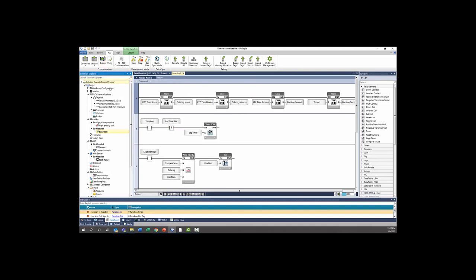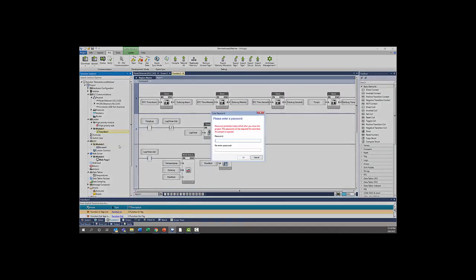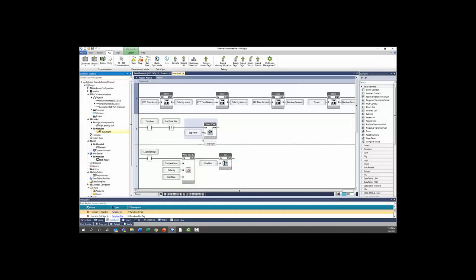In Unilogic, you can also add passwords to the ladder and to the HMIs by hovering over whatever function or HMI you wish to password protect, right-clicking it. And you can select password protect. It will bring up the screen where it will ask you to type in a password and then re-enter that password to verify that it is correct, and then you can press enter there. And now you'll see that there is a little lock next to the ladder icon on function 1, which would indicate that that function is now password protected. The same thing will happen when you password protect the HMIs.